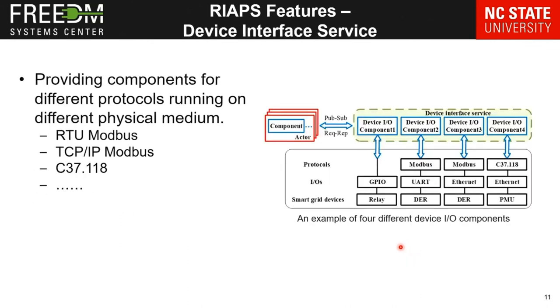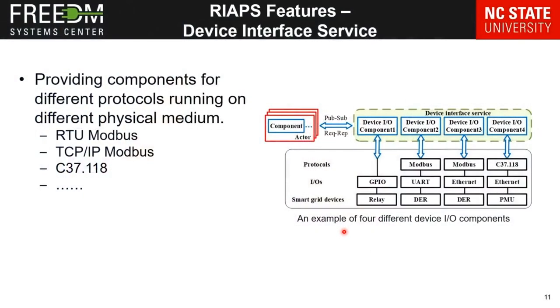The next feature is the device interface service. RIAPS is used to control all kinds of devices in a smart grid, and smart grid devices usually use different communication protocols running on different physical media. For example, inverters commonly support Modbus messages defined by IEEE 1547, and phasor measurement units may use C37.118 phasor transfer protocol. RIAPS device interface service implements those commonly used communication protocols as library components so application developers can use them directly, saving time to focus on their algorithms.